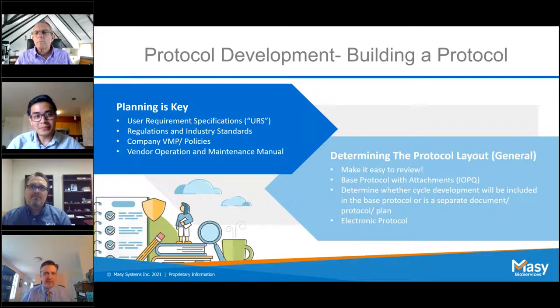So on protocol development itself, what we want to do is give you at least a high level idea of building a protocol if you're starting from scratch, or maybe you're more of a seasoned veteran and you're good to go. The main point, design of your sterilizer and having the right sterilizer for the right process is really the key, making sure that you can actually control some of the things that you're looking to control. But it all starts with getting a URS. You need to know the user requirement specifications for your autoclave. That is key when you're going to be writing up your protocol.